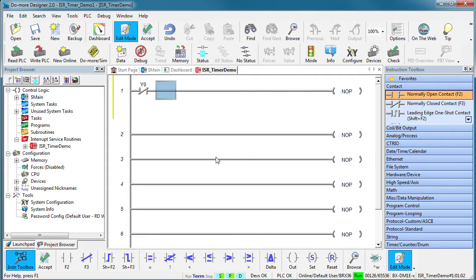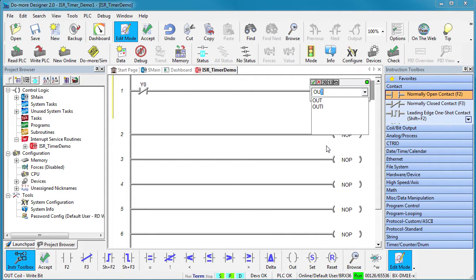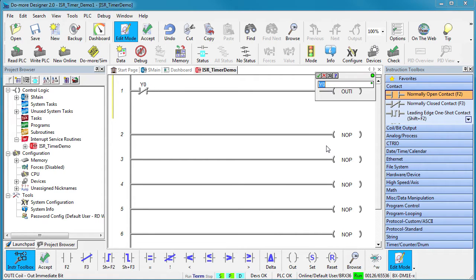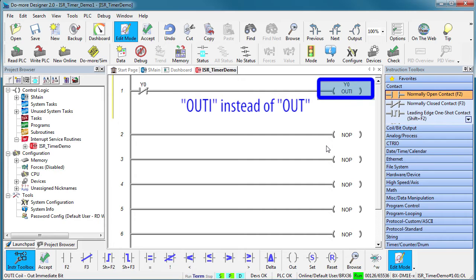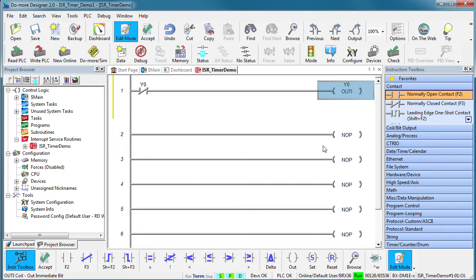In that ISR, let's toggle output Y0 so we can see it on a logic analyzer. Notice that we are using the immediate OUT instruction to toggle Y0. That says set this output immediately - don't wait for the bottom of the scan when the outputs normally get updated.